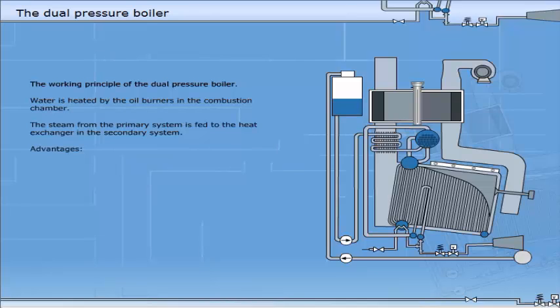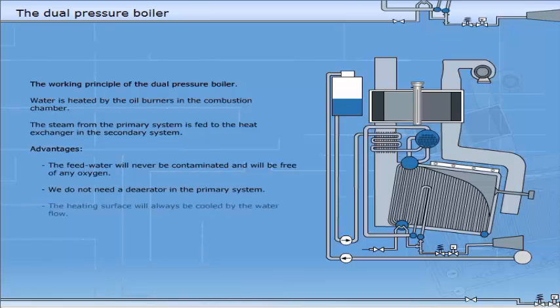As the primary system is completely closed, this system has several advantages. The feed water will never be contaminated and will be free of any oxygen. Meaning that, we will not have any scale formation or corrosion on the water side. We do not need a deaerator in the primary system.